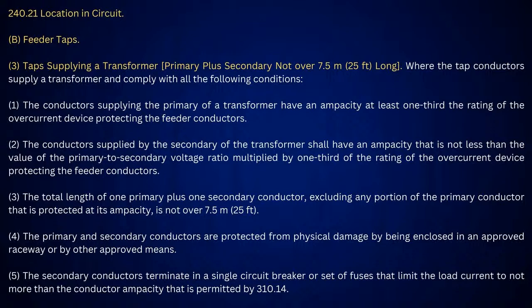Now, look at this. This is where you're doing a tap that's not over 25 foot long, and I have a transformer in that tap. If you look at B31, it tells you for the primary side of that transformer, you have to take it at a third of the rating of the overcurrent protection device. Then if you come down and look at 2, it says the conductor supplied by the secondary of the transformer will have an ampacity not less than the value of the primary to secondary voltage ratio. So I'm going to have to get the ratio of the transformer, and then I take it at a third.